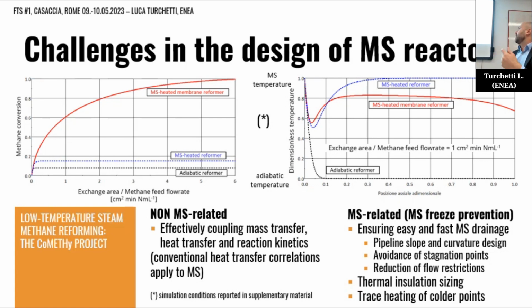This entails accurately designing the pipeline slopes and pipe curvature, because you have to avoid stagnation points where salt can collect when you drain the system. You have to reduce any flow restrictions because you don't want pressure drop — the drainage must be very fast.